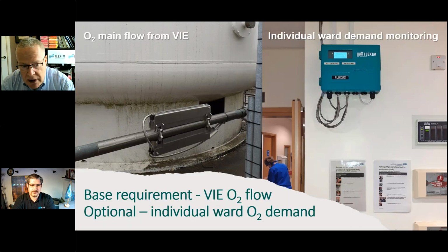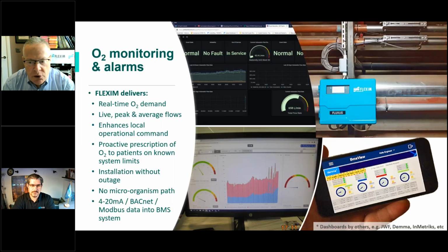So the bare minimum is one meter on your VIE, as you see on the left-hand side in the compound, but equally, for extra granularity, we can do individual ward demand. The O2 monitoring is giving you real-time oxygen demand. There's none of this hourly reporting or even daily reporting for tank replenishment. It's giving instantaneous live peak and average flows. That's obviously enhancing the local operational command within the actual hospital, and proactive prescription of oxygen within the known limits of the system.